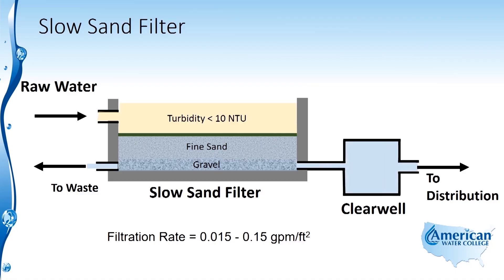For a slow sand filter, as its name indicates, the filtration rate is very low — in the range of 0.015 to 0.15 gallons per minute per square foot of filter surface area. It's got a very low flow rate in relation to the surface area of the filter, and that's why it's called a slow sand filter.